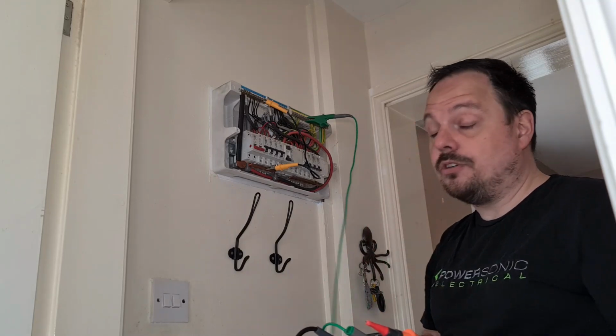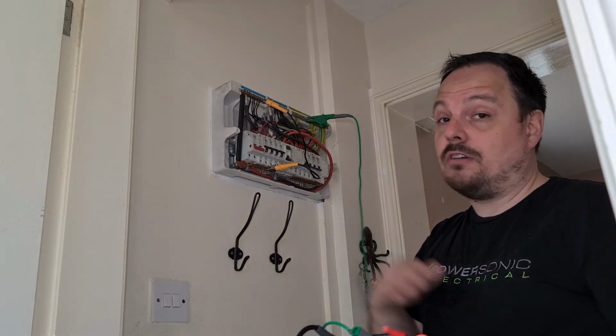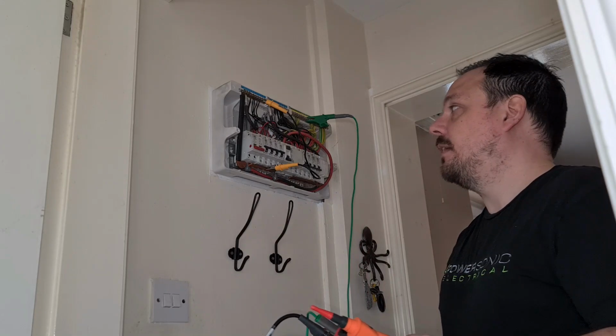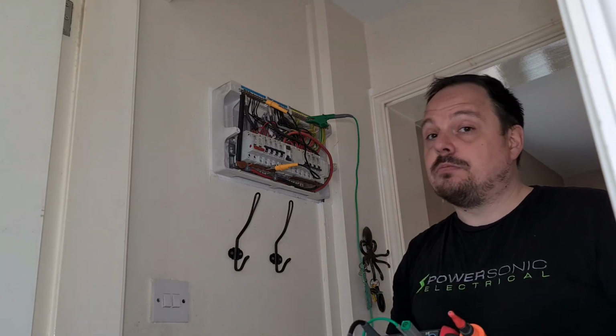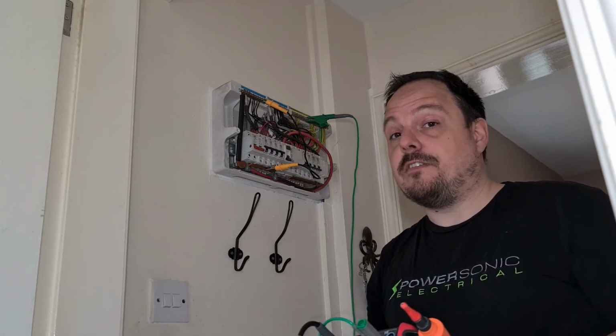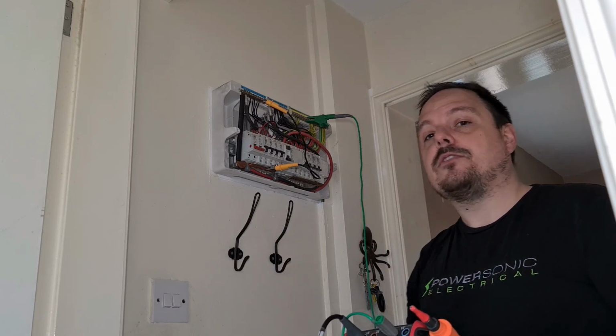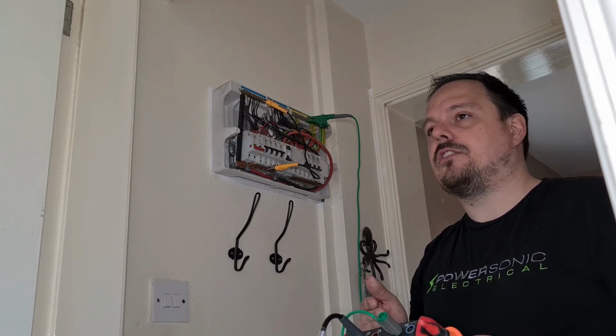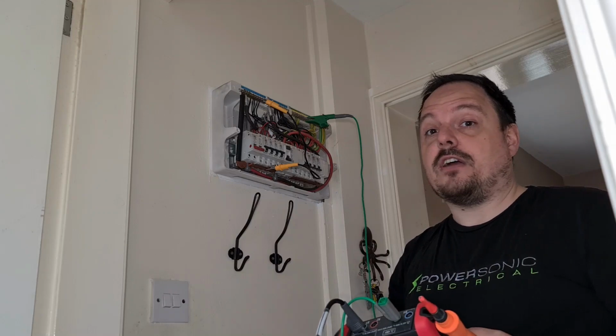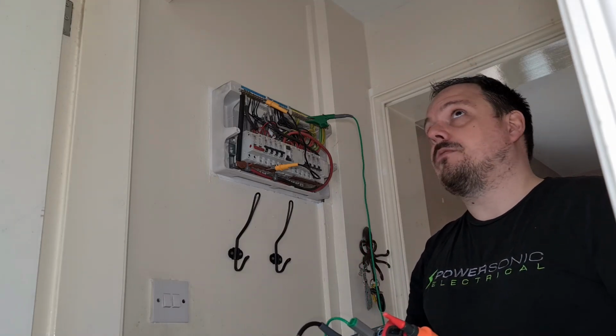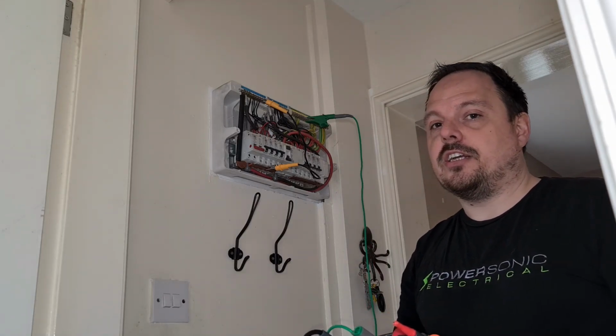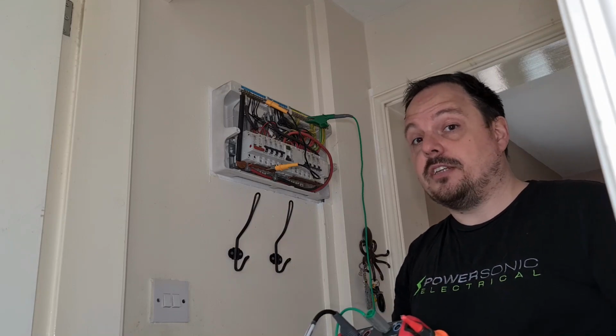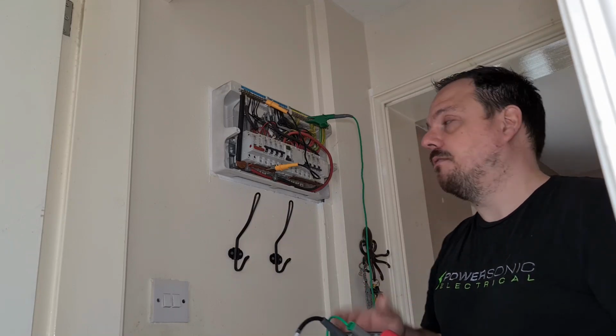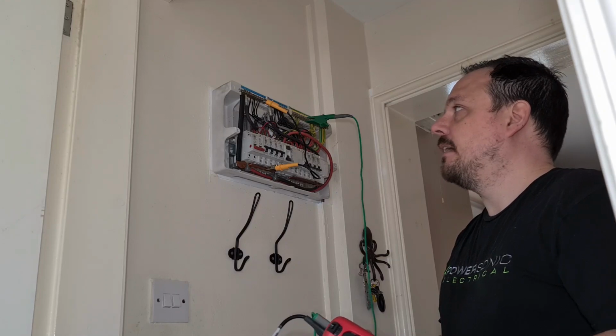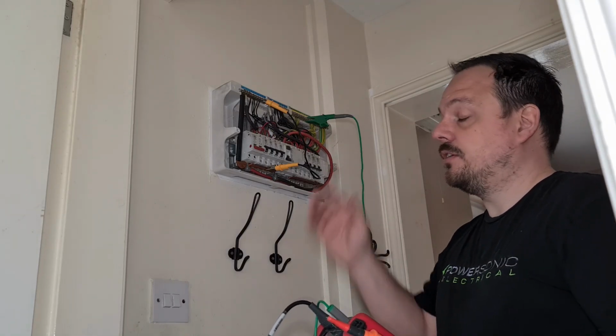So we have that measurement, and it's fine, it's clear. It's measuring 210 megohms. It's not reading off the scale, but it's plenty high enough, and that's probably due to the moisture ingress into the final accessories that I was worried about. While the building's been dried out, those terminals will have some sort of tracking through them, so at the very least we're going to have all of these circuit accessories changed. When that process is completed, those values should rise back up. I can verify that on one or two of the circuits, which I'll do now.